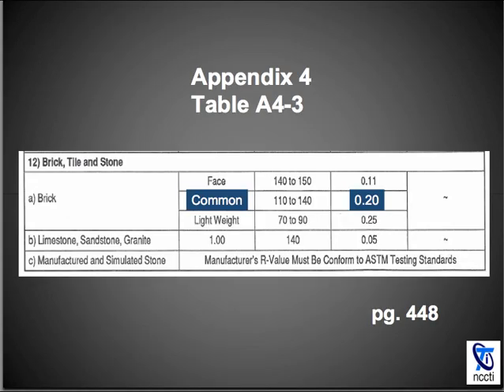Get your Manual J8 out. Turn to page 448, appendix 4, table A4-3. Under number 12 — brick, tile, and stone — A brick, the face is common, and it's R 0.2 per inch.